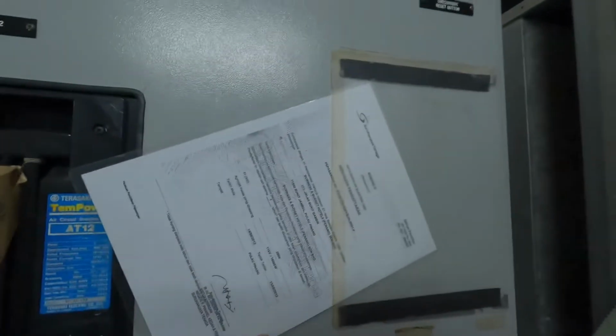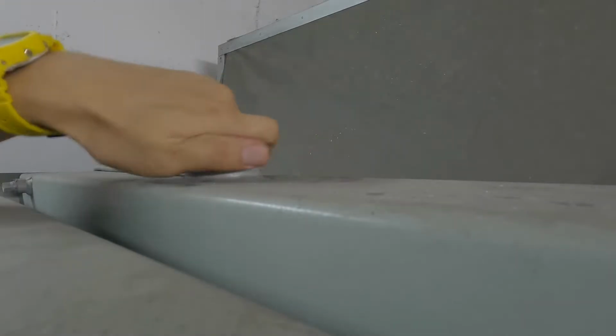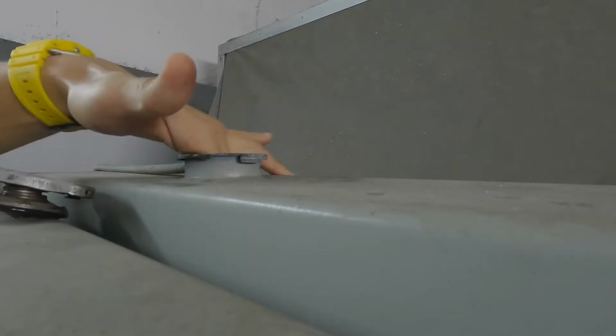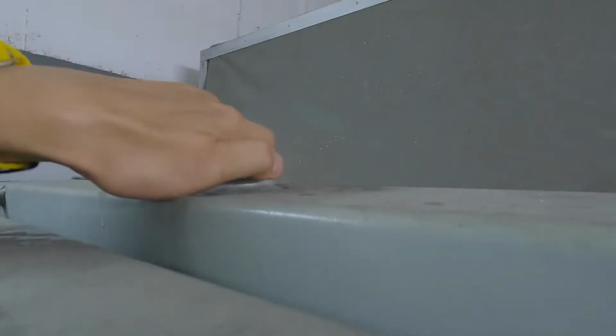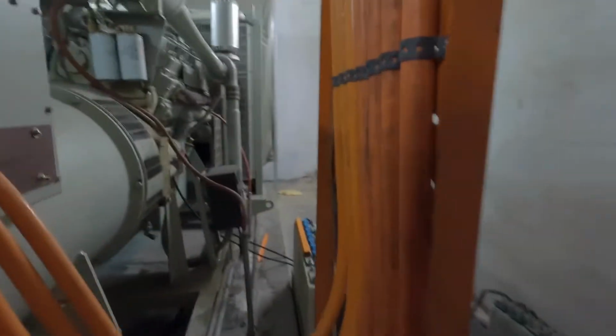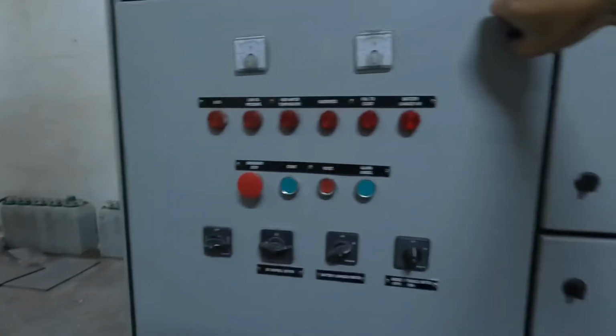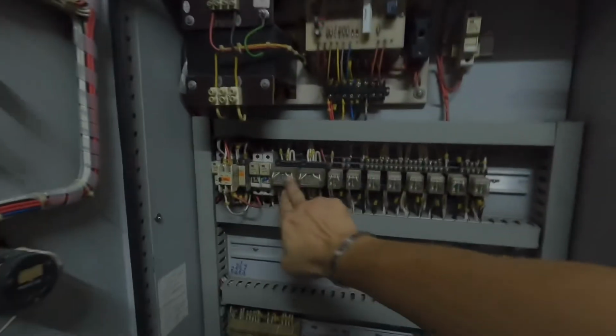Okay, Borang B just recently renewed. Okay, now we are going to check the radiator water level. Okay, the water is clean, available and sufficient. Alright. Okay, this is the genset AMF panel. Currently it's set at auto mode. Okay, we're going to test run it one time using test mode. Okay, we test.